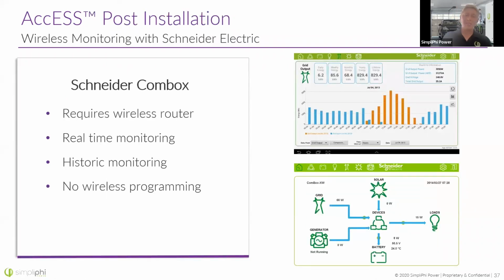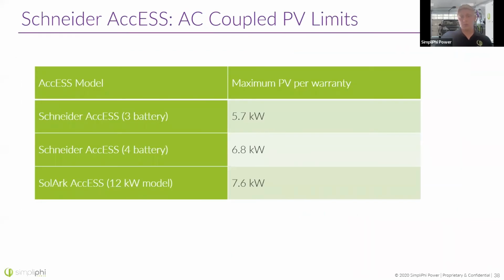With the Schneider Access unit, you will need a Combox for the monitoring to work. This requires a wireless router. There is real-time and historic monitoring, but last I checked, there is no wireless programming. So remember about the PV limits, and we're talking about AC coupling here. Do not overload the battery-based inverter. It will charge the batteries too quickly and can damage them.